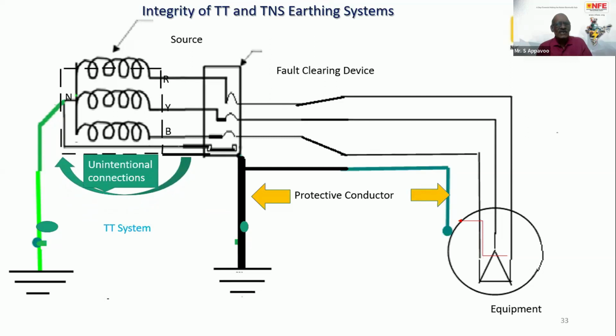So another part is, we are providing a TT system. We think that it is a TT system, but in actual field reality, the armor is connected to the equipment frame. That is the source, transformer or generator. The frame is connected either through the bus duct or through the armor. Then the neutral earth electrode is connected to the body earth electrode of the transformer or the generator. Here you are having unintentional connections.